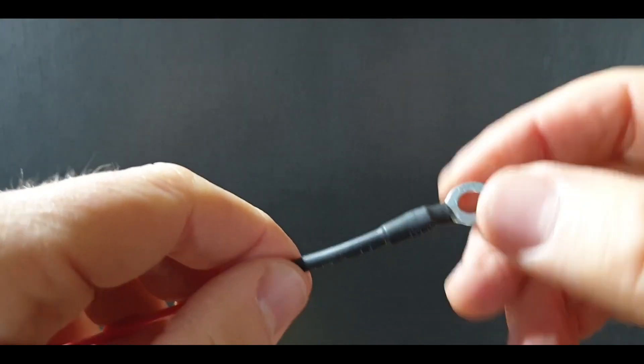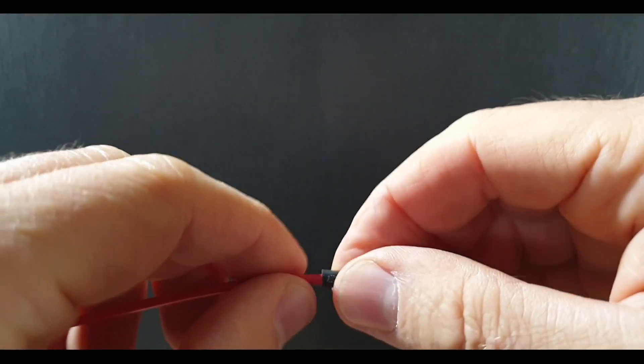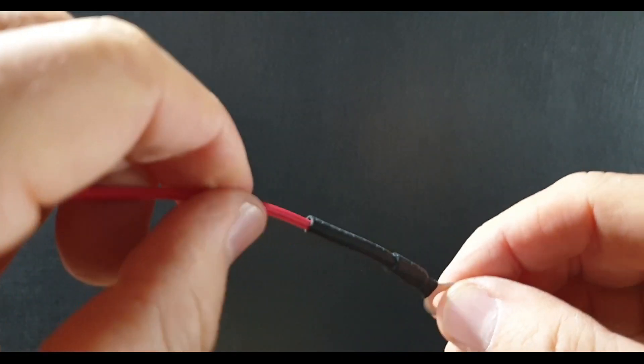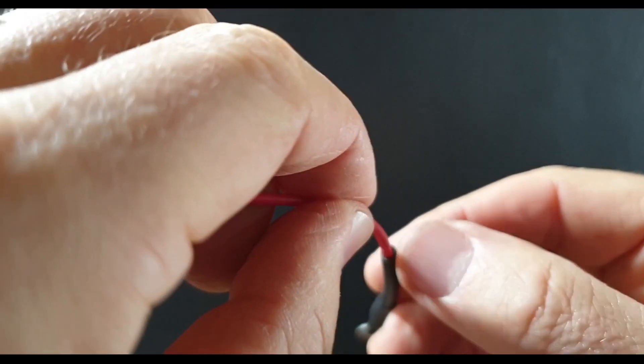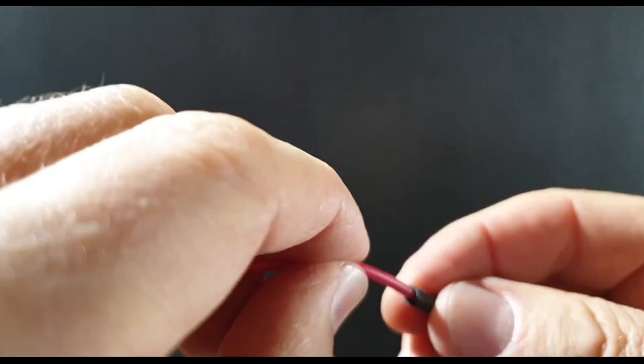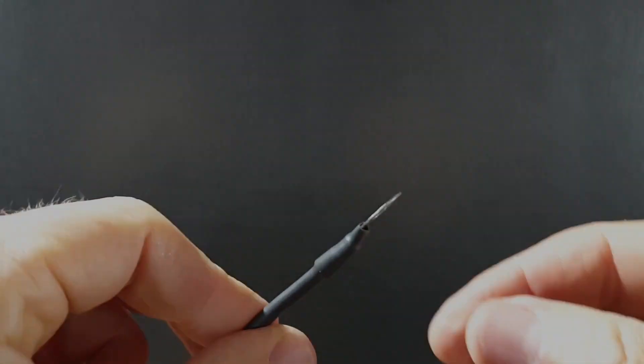Now ideally this would be self-adhesive heat shrink, because then what that does—the glue inside melts, squeezes out, and forms another waterproof seal. What you can do is if you think this is going to be a little bit too slack, you can put a smaller size on first and shrink them both down together, and that will take up any slack. But that gives you a much nicer waterproof or water-resistant connection.